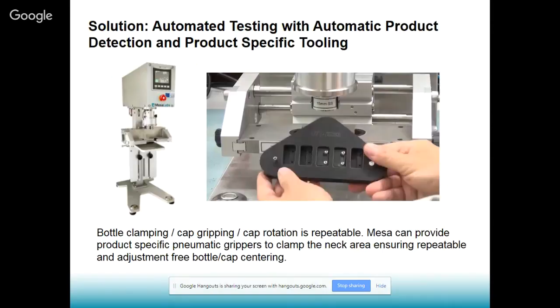And from that perspective, again, automated torque testing has a huge benefit because the rotation of the cap is fully automated. And this slide is just showing you again that you can use an automated tester and just place the bottle on it and press the 2 push buttons. It will always clamp it the same way, always grip the cap the same way, and always ramp up the torque the same way.